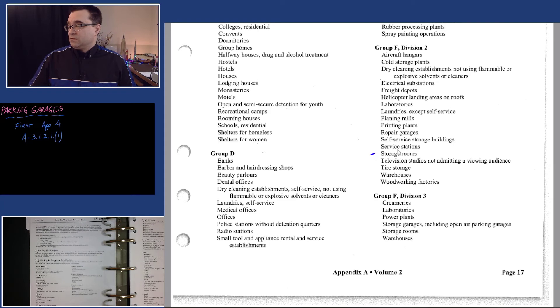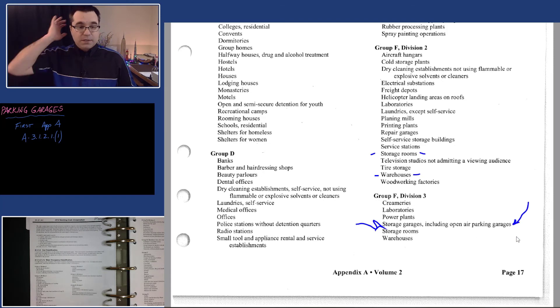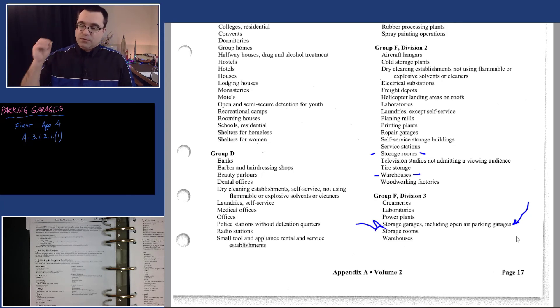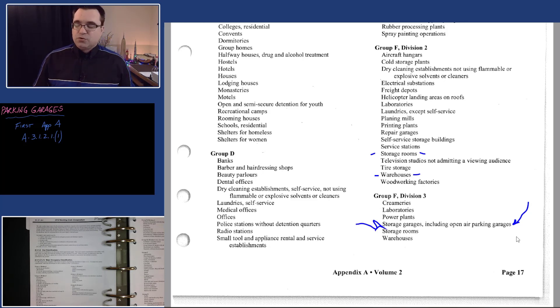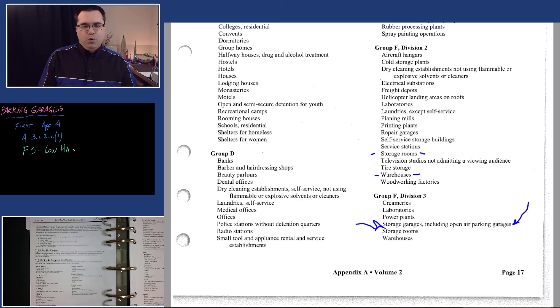F2 mentions storage rooms and warehouses — maybe, but not quite a parking garage. F3 — look at this: 'storage garages including open-air parking garages.' That's exactly what we're looking for — a place where you drive your vehicle and it gets put into storage, because parking is storing your vehicle. So F3 is a good candidate. F3 is low hazard industrial.